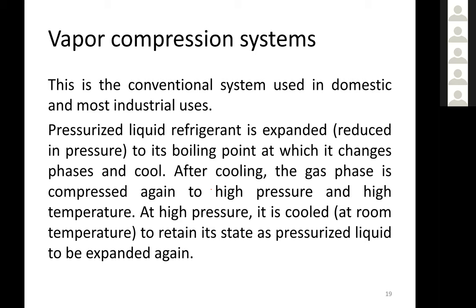And here, as I just described, pressurized liquid refrigerant is expanded or reduced in pressure to its boiling point, at which it changes phase. So we need to bring it down to a pressure value that corresponds to the desired boiling point. And of course, after cooling, the gas phase is compressed again by the compressor, then it goes to the condenser and back again to the expansion valve.